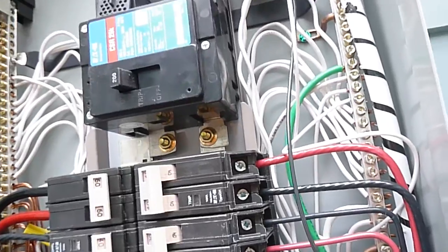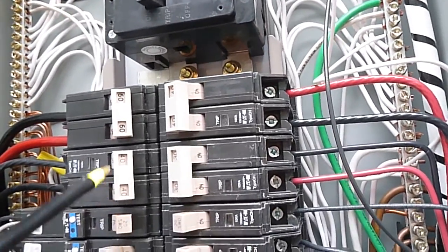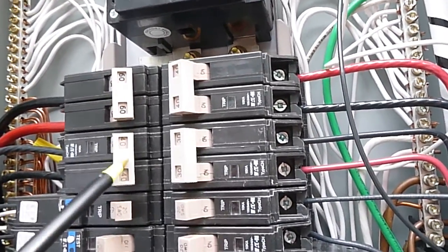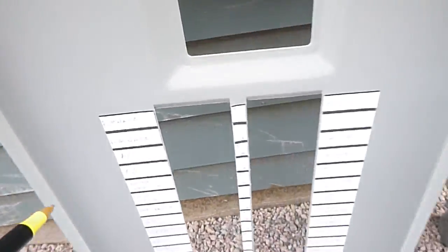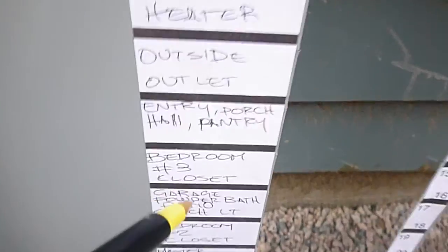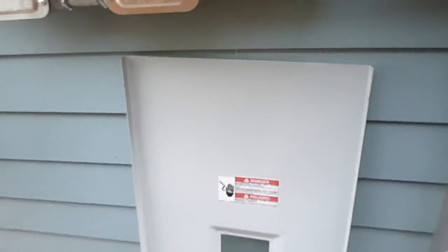The HVAC air conditioning condensing unit is overfused. It's a 30 amp maximum fuse, and that's a 40 amp fuse. You're also supposed to have a directory. Okay, you see this schedule here? It's got everything listed on it. Well, this schedule's blank. You're supposed to have a directory, and it's not supposed to be handwritten. It's supposed to be printed. And then this meter box is sealed. Actually, the sealing all looks pretty good.